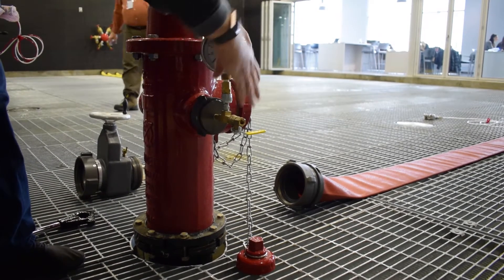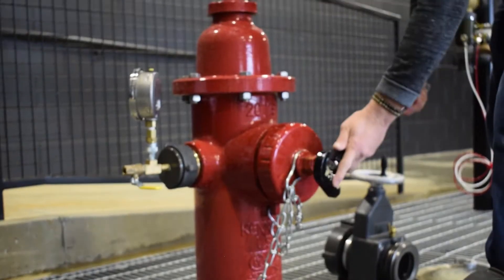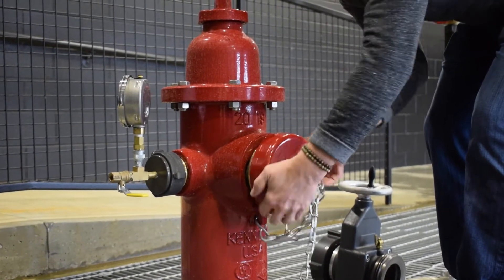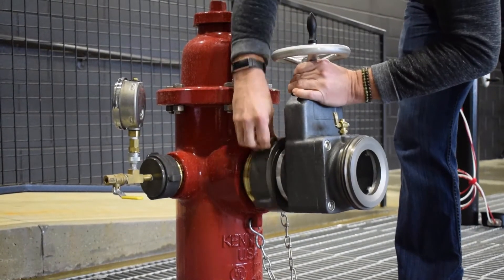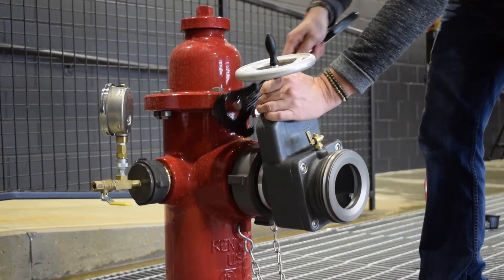Attach the static residual pressure gauge. Remove the hydrant cap from the pumper port and attach the hydrant gate valve, making sure the gate valve is in the closed position.